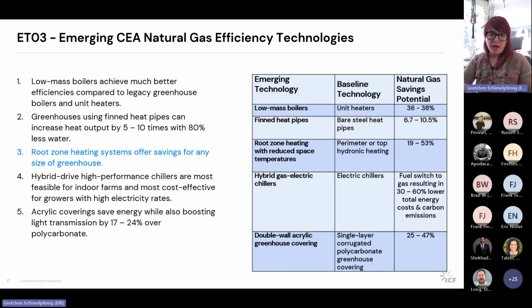And so we found that there's a new product that allows the facility to use both gas and electricity for chilling, and the equipment itself is given information about the cost of electricity as well as the carbon emissions of the grid at any particular time, and it can choose to use gas or electricity depending on cost savings or emissions savings. And so we found that initial studies show 30 to 60% lower total energy costs and carbon emissions. And this could be most effective for growers with high electricity rates, which would encourage them to use the gas side of the chiller. And also growers with perhaps dirtier grids could also be a good opportunity there.